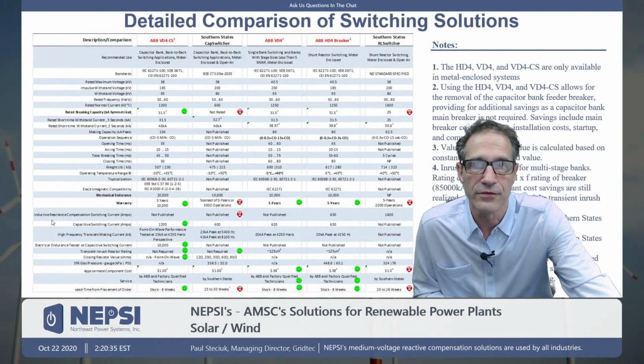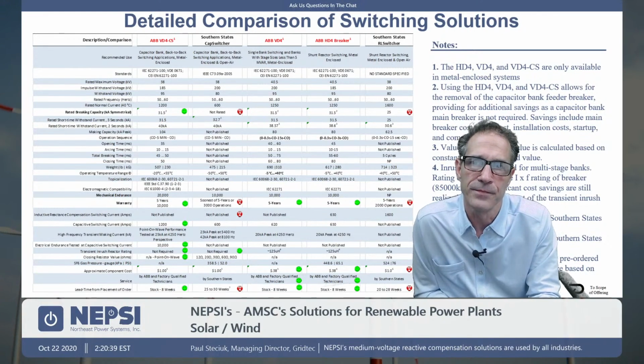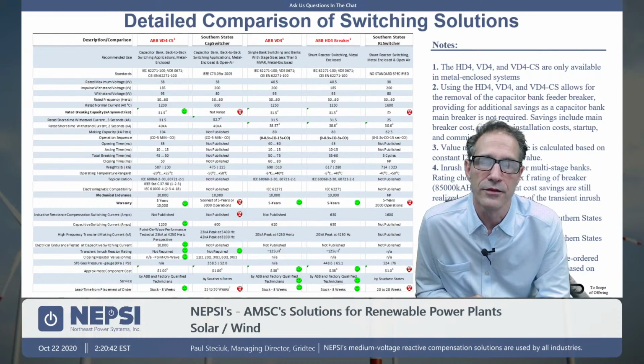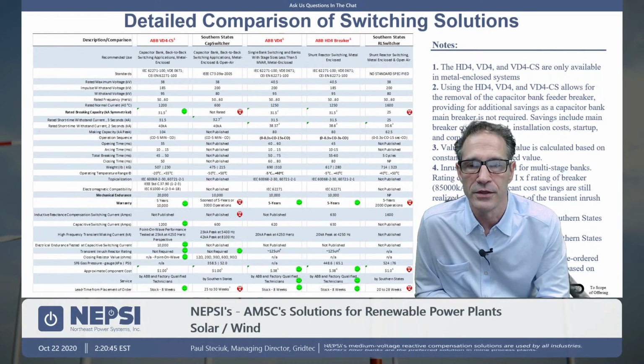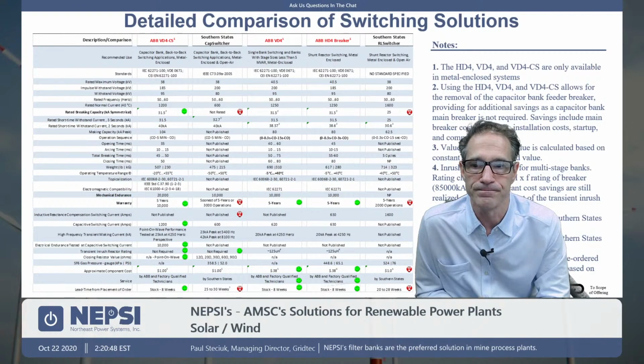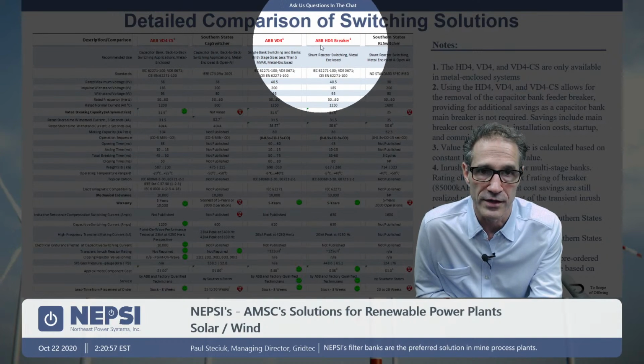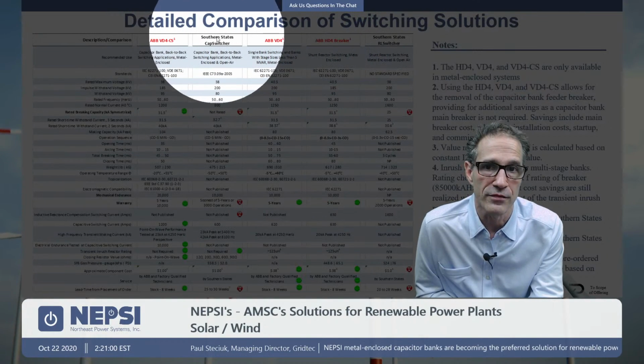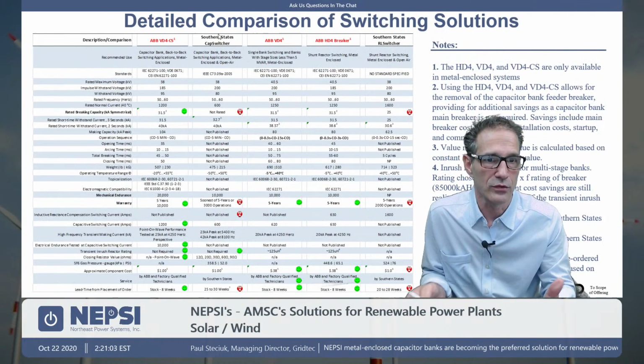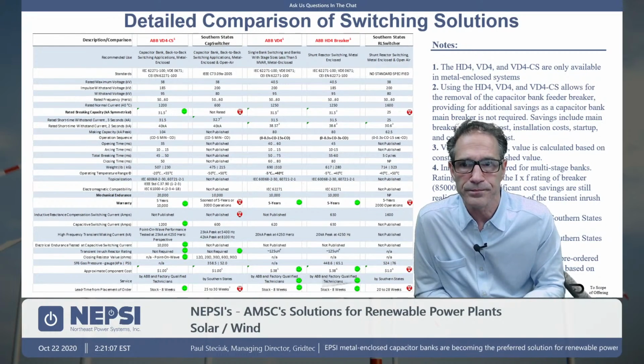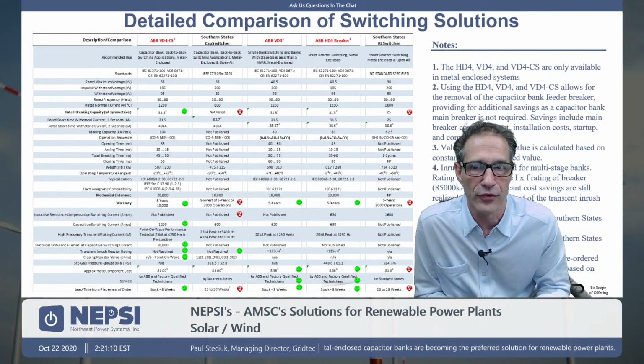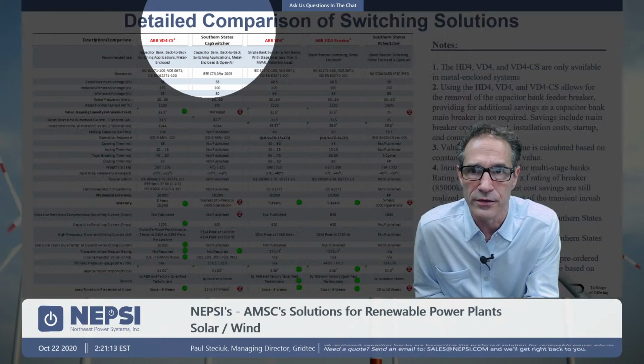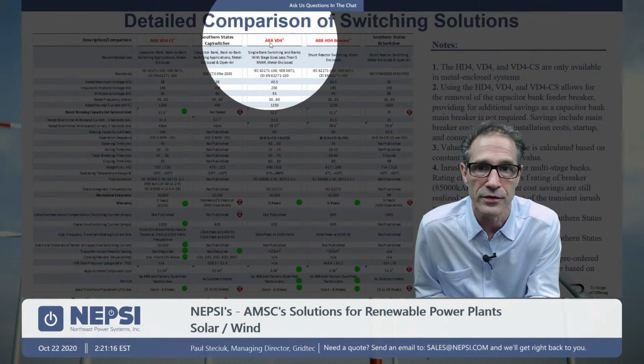This is a comparison of switching options, and when you think about what switching devices are available to you as a customer purchasing capacitor banks, you have a choice of breakers, and we list them here, the VD4CS and VD4 and HD4. But you would also have the Southern States cap switcher, which, by the way, is an outdoor solution. So if you go with the 150 kV BIL and 31.5 kA, it allows us to squeeze into using these other breakers. Okay, so Southern States cap switcher is a switch, it's not a breaker.